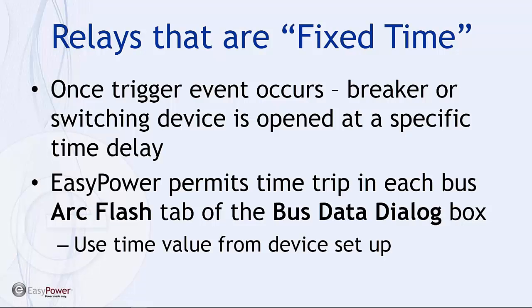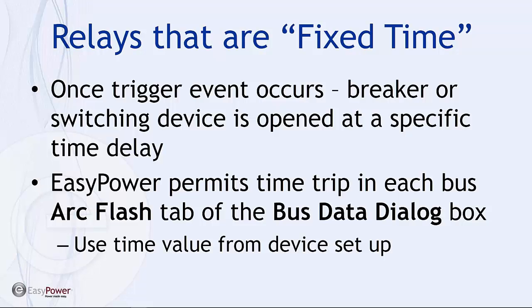That is something that can be adjusted, but it's more a function of the hookup or daisy chain or intentional delays that are set into the device. It has nothing to do with how long the fault itself lasted to initiate the trigger. And likewise with differential devices. Easy power permits, and when you think about this, a short circuit study has no relevance to time in terms of what the impedance calculations and what the current calculations provide. That's where we're going to dovetail into the discussion about time current characteristic curves, because that is the common denominator that allows us to look at time when it comes to tripping devices and fault currents.